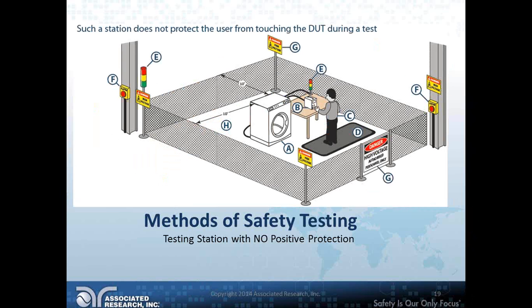In this case, we also have a big high voltage sign on the door of that screened-in area. That's the other important thing to point out: the screened-in area guards against anybody getting in there if they're not a qualified operator. That's a smart thing to do. It doesn't have to be a full fence, just roped off—like those yellow chains with pylons, or tape on the floor marking a danger high voltage area, a 10-foot space, so unqualified people can't get within there.